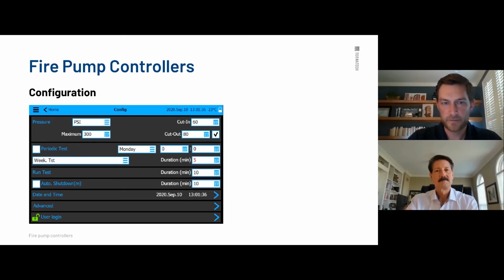You would change that down here where it says weekly test. You can drop down this menu and change to how frequently you want it to come on, as well as what day and what time and for how long you want it to run. So a lot of people don't use that periodic test. One of the things with running your test is that somebody is supposed to be present at all times. If the pump is running, somebody needs to be in the room. And in that case, you could just push the button. So it's not necessary to set it up to come on automatically, but it is an option.